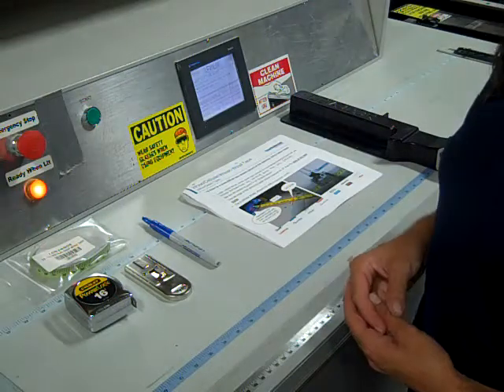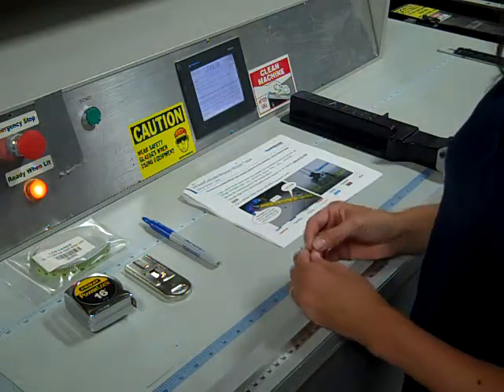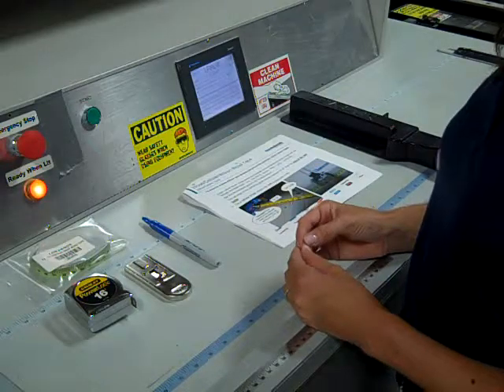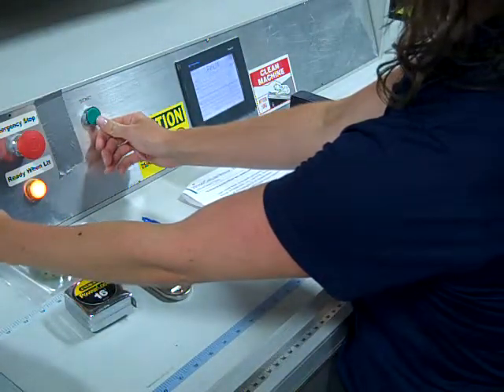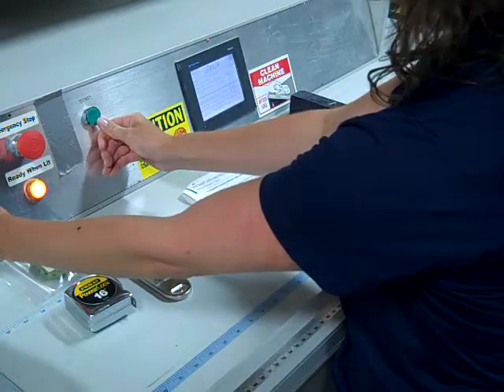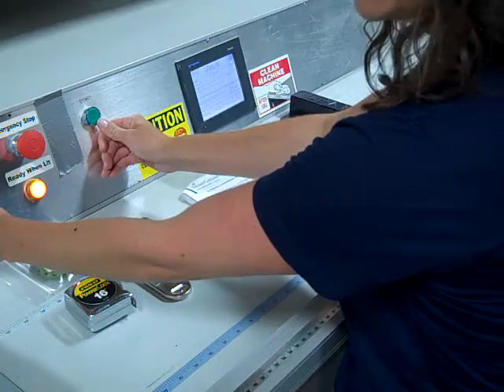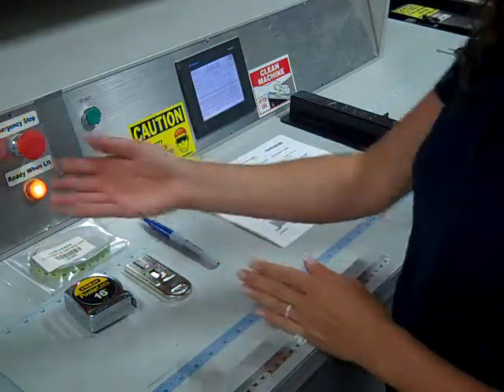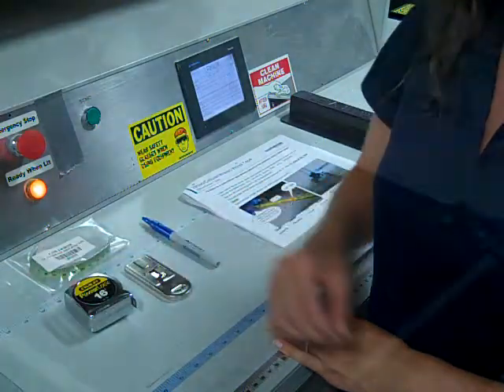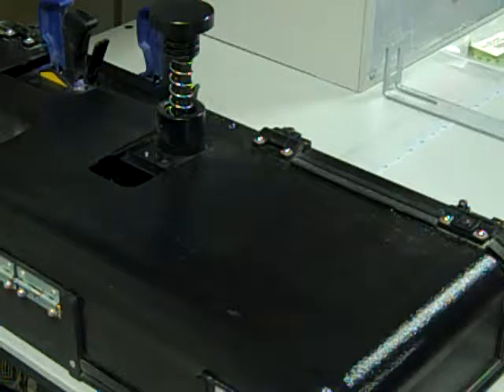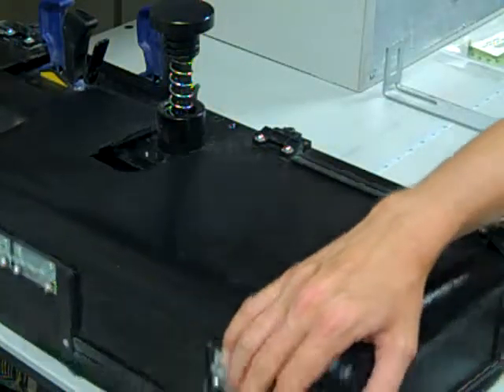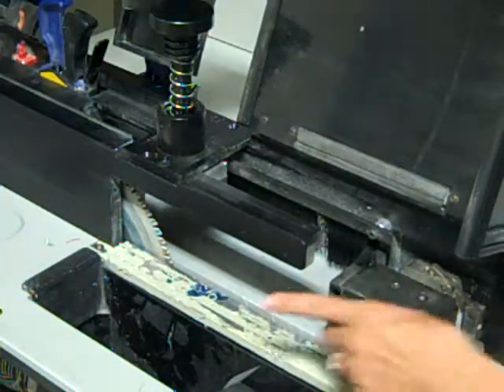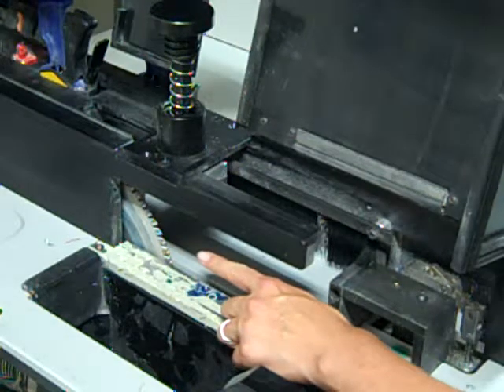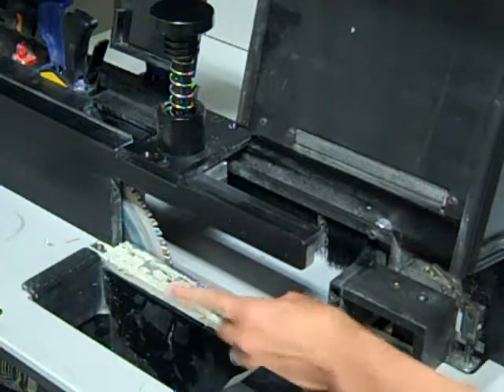Next, to ensure accurate calibration, we are going to move the blade in the machine into the cut zone. The way you will do that is to press both green start buttons and hold them down for 15 seconds. I have already done this for time purposes, but you will hold it down for 15 seconds to simply move your blade into the cut zone so we can measure from the blade. Next, let's check the blade location so we can ensure we measure our calibration tape accurately. You will want to raise the black hood on the left side of the machine and ensure that your blade has traveled into the cut zone so we can actually measure from the blade. You will next want to lower the black hood on the left side of the machine.